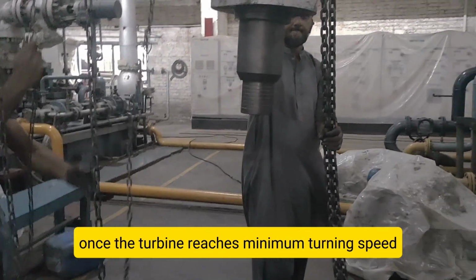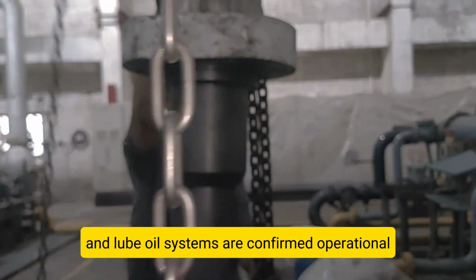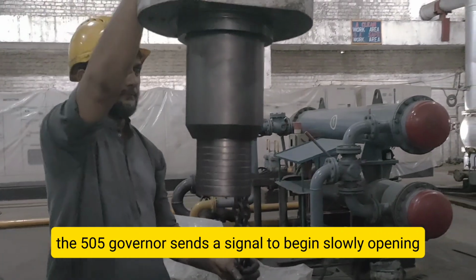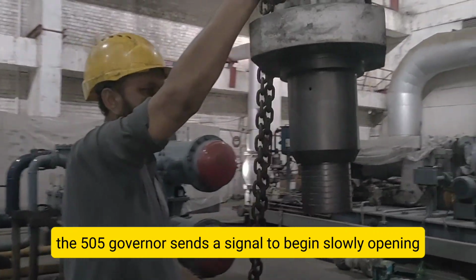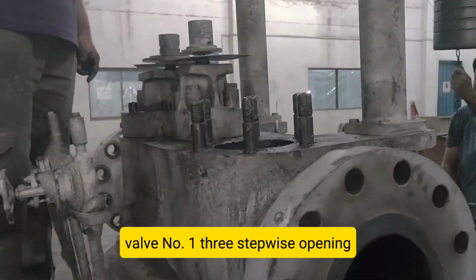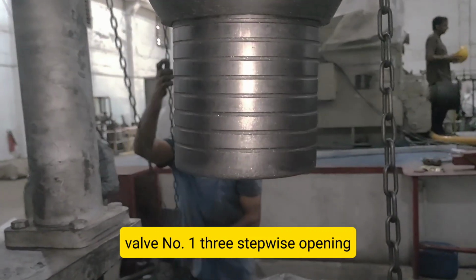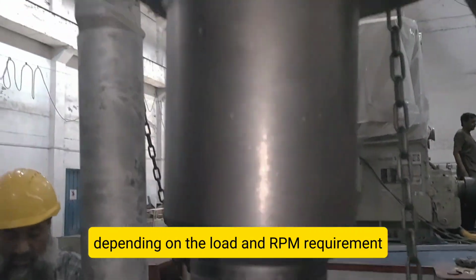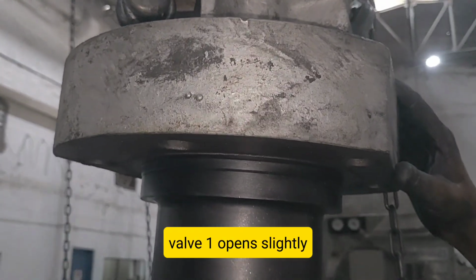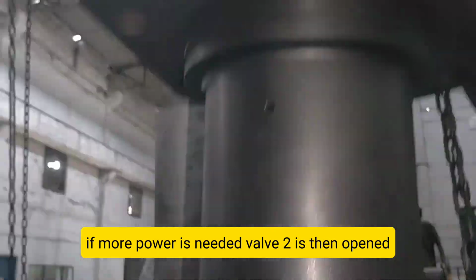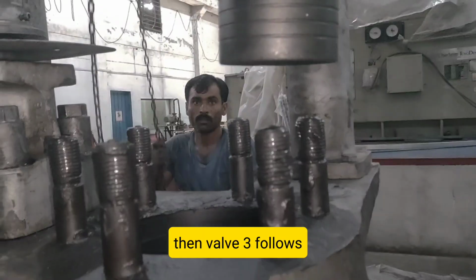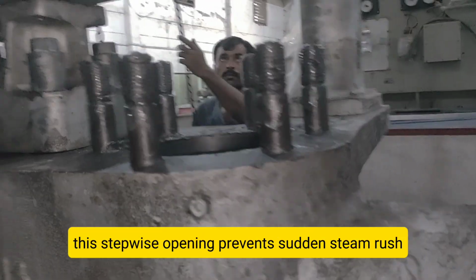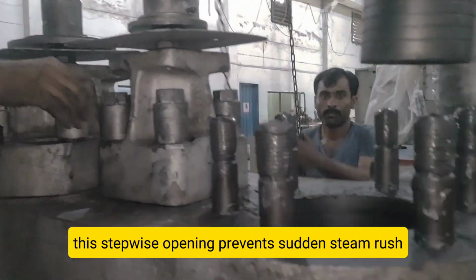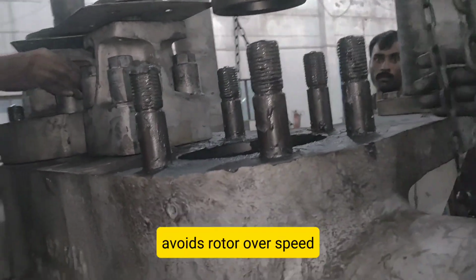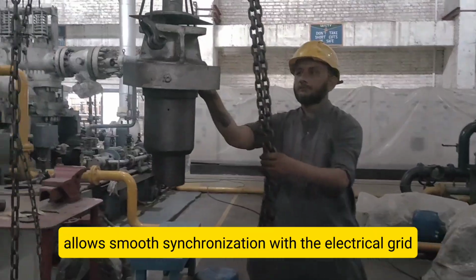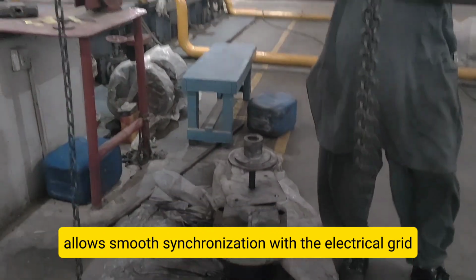Throttle valve operation, step by step. The throttle valve controls how much steam enters the turbine. Here's how it operates step by step. 1. Valve closed, startup. At turbine startup, the throttle valve is fully closed for safety. 2. Initial opening. Once the turbine reaches minimum turning speed and lube oil systems are confirmed operational, the 505 Governor sends a signal to begin slowly opening valve number 1.